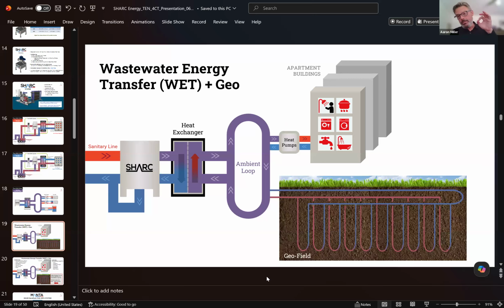When they did the initial analysis, they said, okay, all electric, no gas building. We're going to need 128 boreholes at 500 feet to cover the whole thermal load of the building. Great. Let's drop SHARC into the energy model and do some heat recovery. Surprise, because of the passive house design of the building, the building envelope is so tight, it doesn't need a lot of heat. It needs cooling. It's a very cooling dominant building.